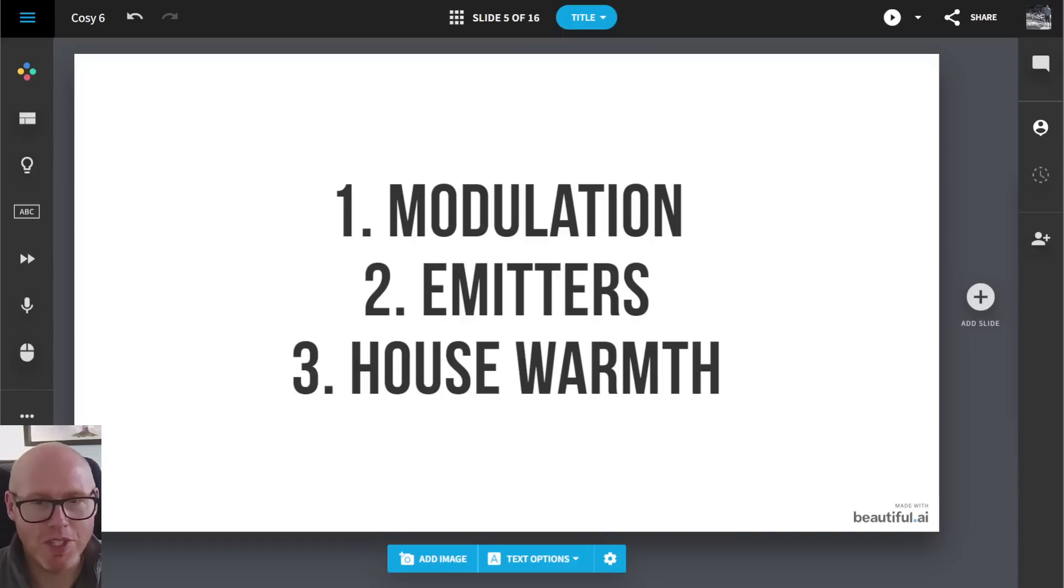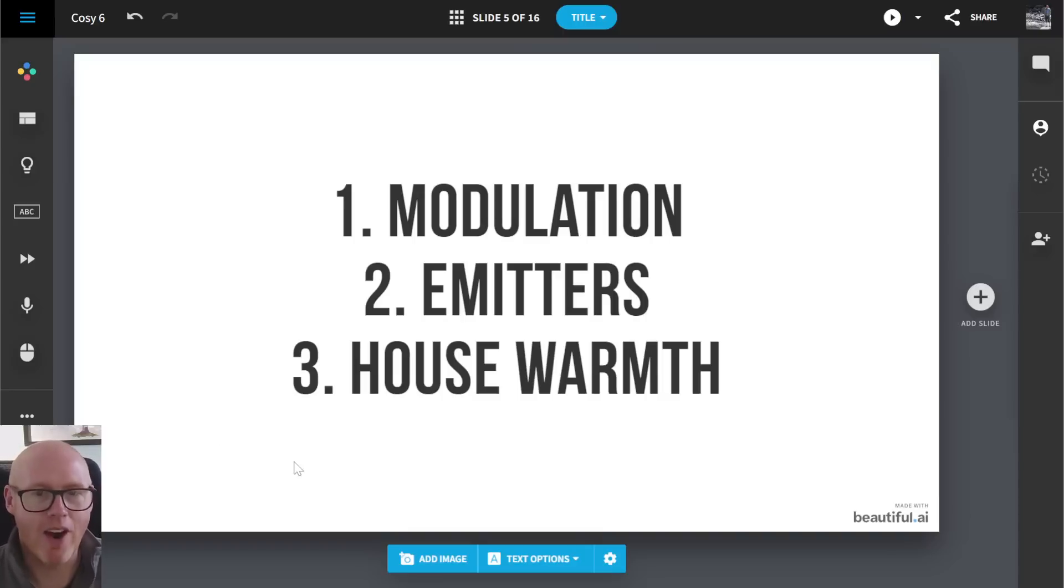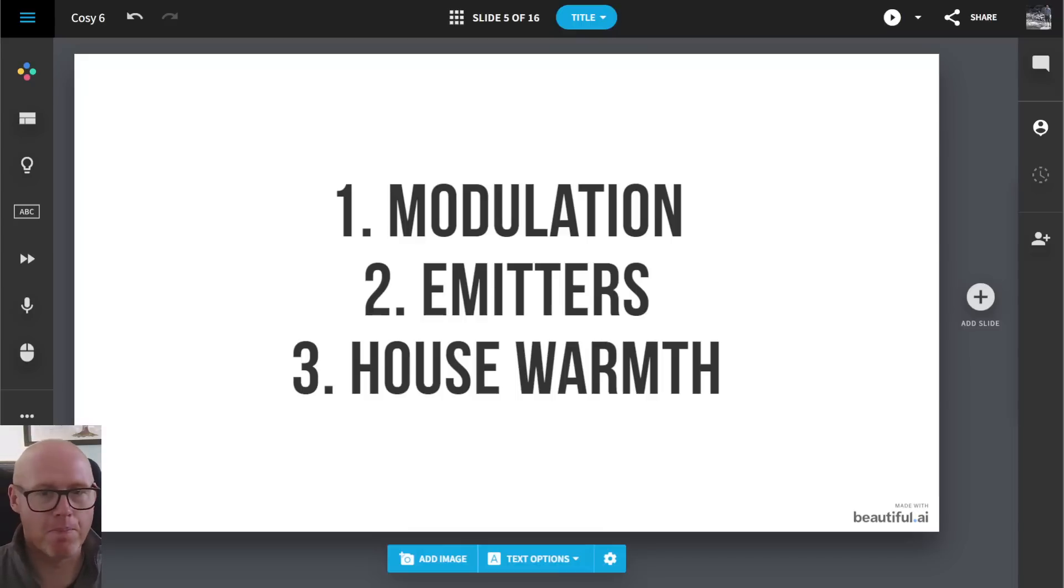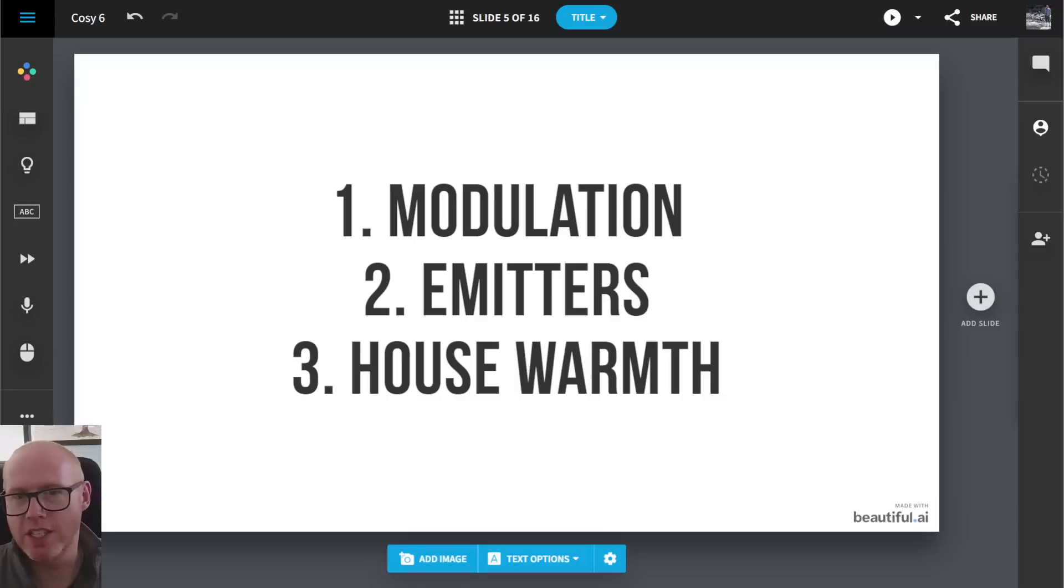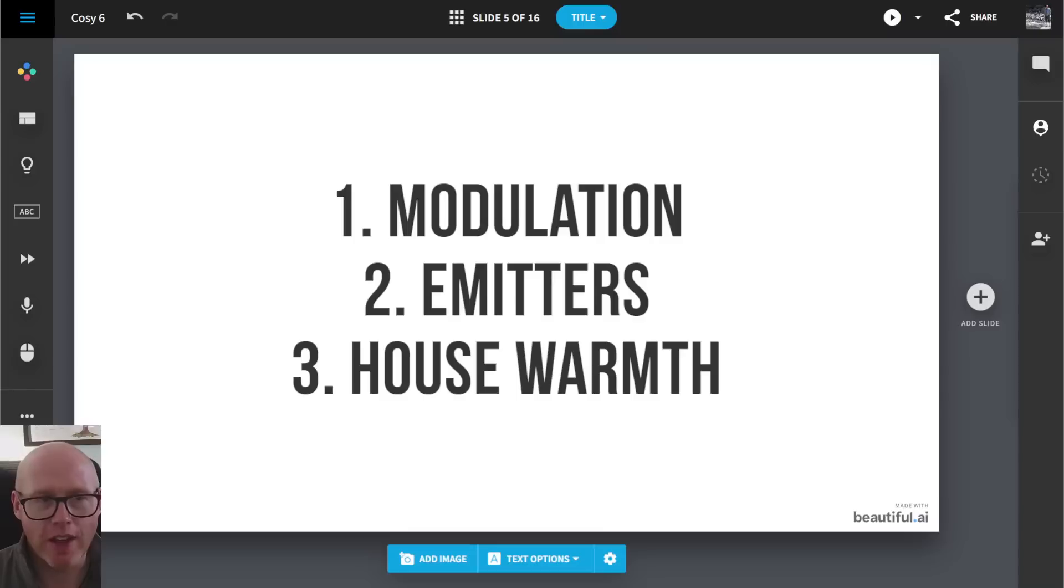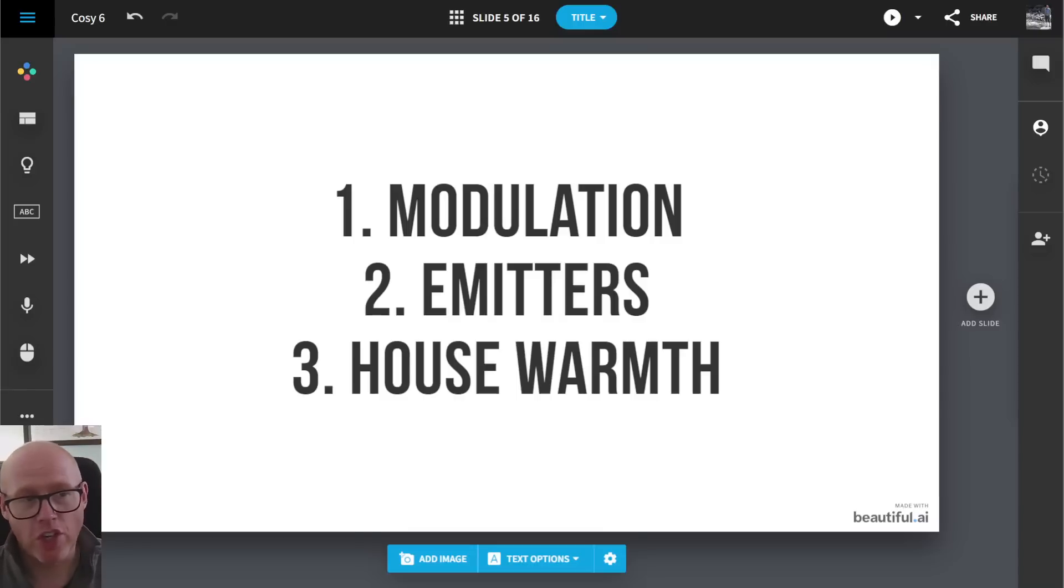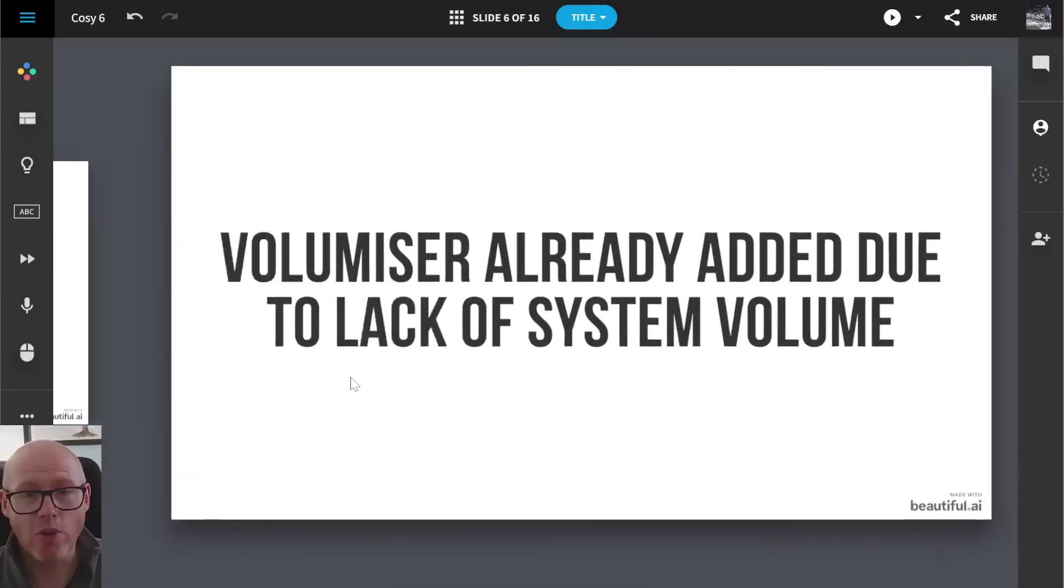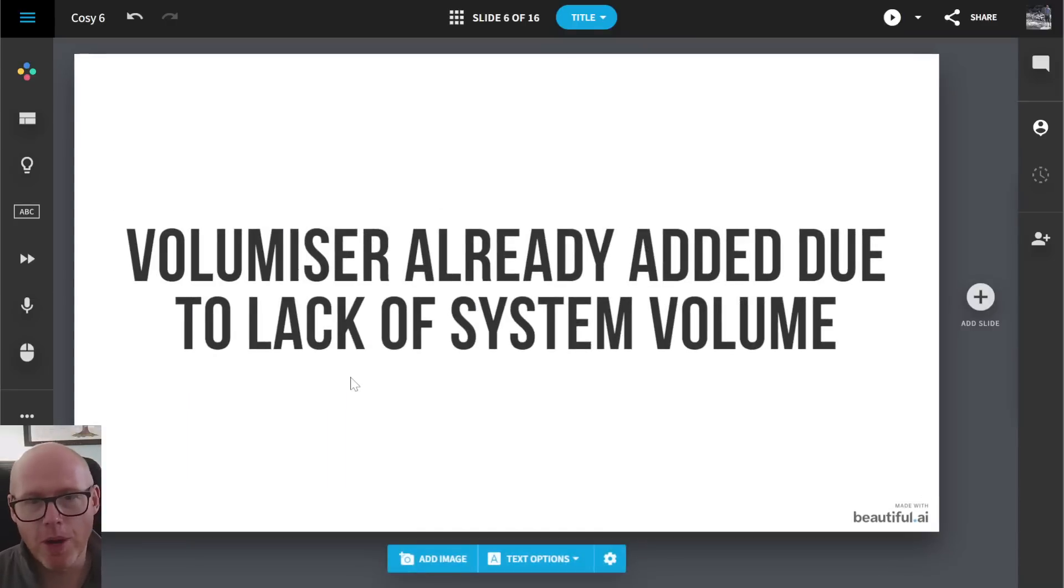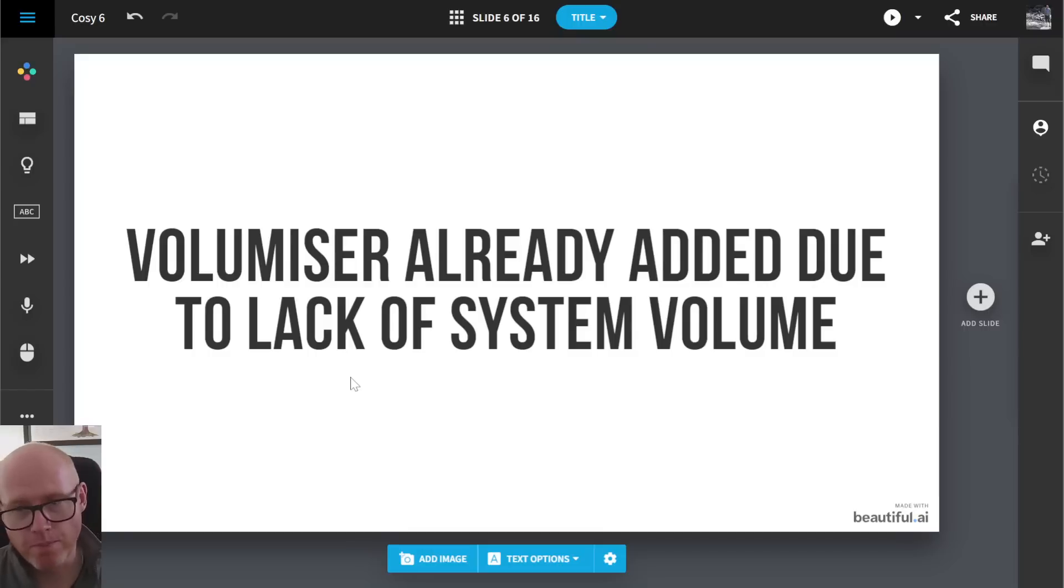And we don't know yet until we see the full data exactly how Octopus are managing that situation. So emitters and Nick says in his video that potentially he doesn't have big enough radiators or a big enough home to shed all of that heat. But, you know, there will be an issue that if you turn down the weather compensation curve too much that your house might get cold.